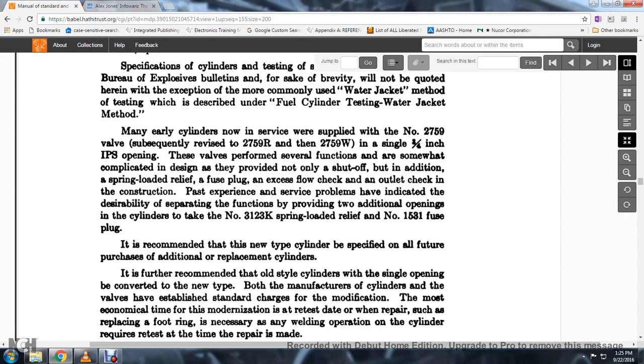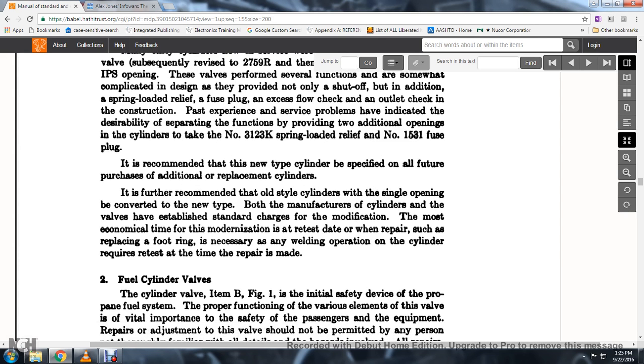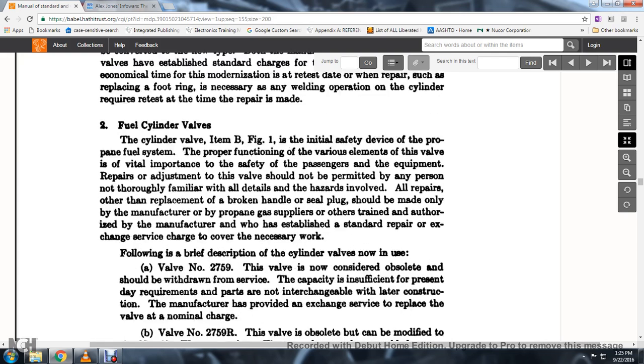Past service experience has indicated it desirable to provide additional openings in cylinders, which take the No. 3123K spring-loaded relief and No. 1531 fuse plug. It is recommended that the new type of cylinder be specified for all future purchases. For the conversion of old single-opening cylinders, the most economical time for modernization is when the cylinder is retested or when welding operations on the cylinder require retesting.